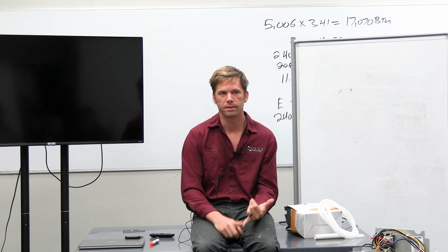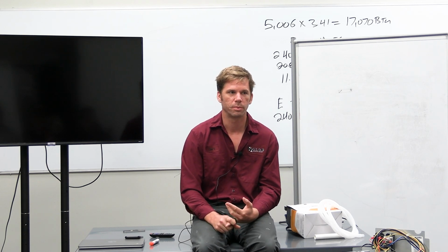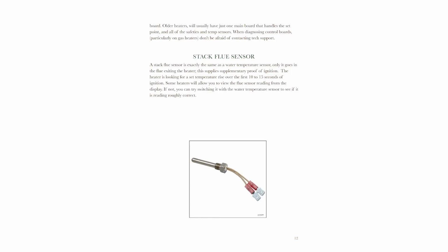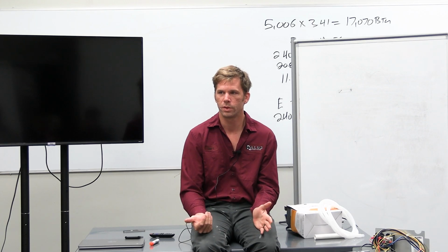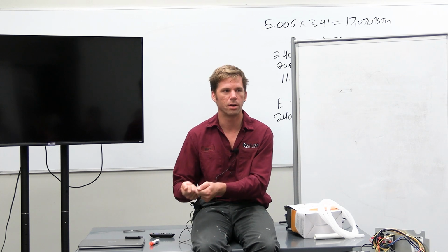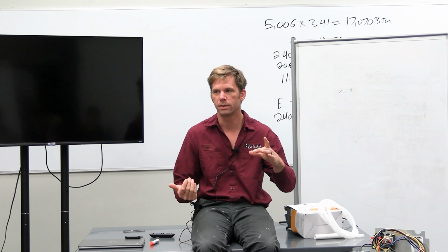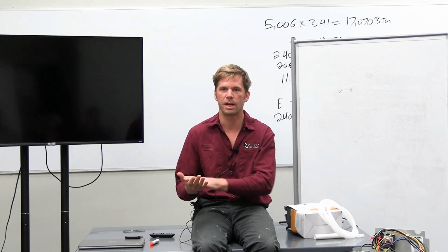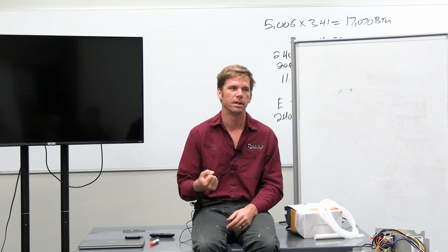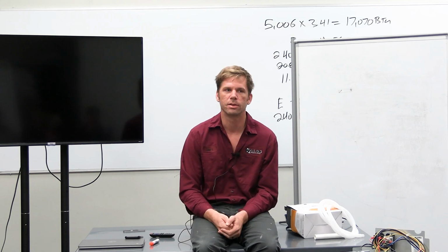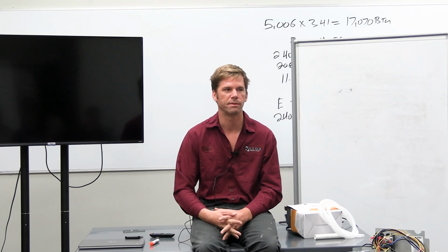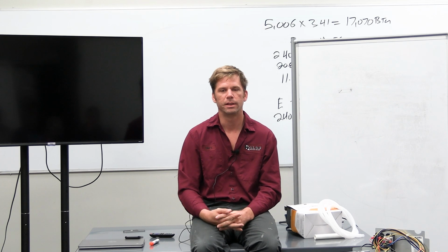They deal with outside weather and really hot temperatures. They're plugged into that exhaust pipe. Usually if you pull up the manual, they'll have a chart that you can actually test your stack flue sensor with. A stack flue sensor is the same as a water temperature probe. So you can actually pull it out, hook it up to the water temperature input, and then use the display of the board and it'll read. And if it's reading the same temperature as the outside air or your hand that's holding the stack flue sensor, then you know this thing's actually working. So that's not my issue. I don't have a failed sensor. I have an actual problem going on here that I need to address.